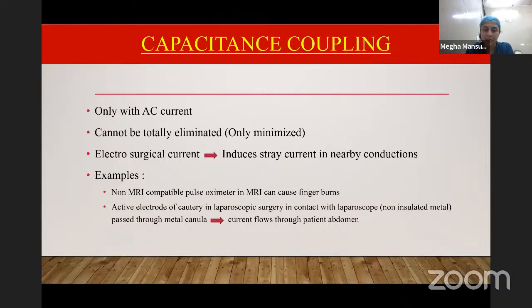If there is an electrosurgical current present, then it can induce a stray current in nearby conductors. Examples of capacitance coupling are a non-MRI compatible pulse oximeter in an MRI room causing finger burns. Or, if the active electrode of cautery in laparoscopic surgery is in contact with a non-insulated laparoscope, and this is passed through a metal cannula and current flows through this, then it can flow through the patient's abdomen and lead to burns.